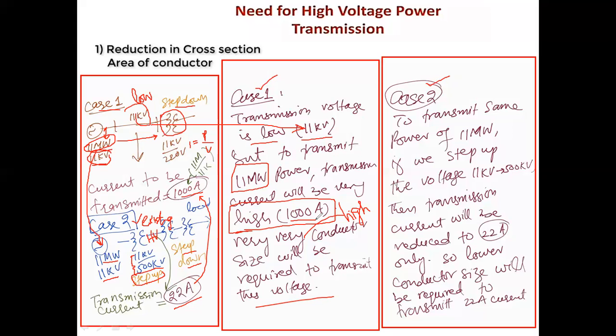And according to the book, for example, if we take a table tennis table and consider it as the diameter for that conductor, so assume a circle around the tennis table. That will be the cross-sectional area for the conductor of 1000 ampere of current. So a huge amount of current, and this is only for one phase. So two more conductors of the same size will be required to transmit the three phase current. So that is a huge amount of current. We will have a high conductor size, so it will be quite difficult for us to transmit.